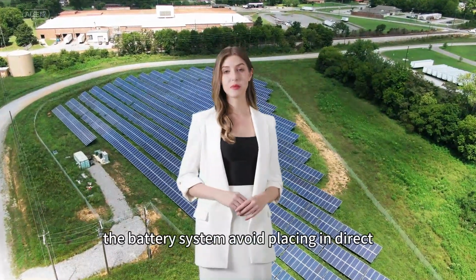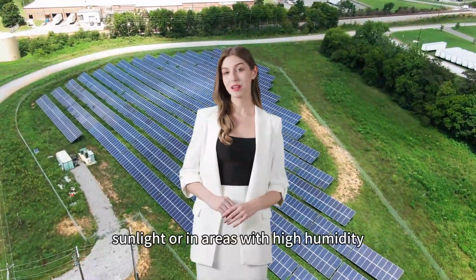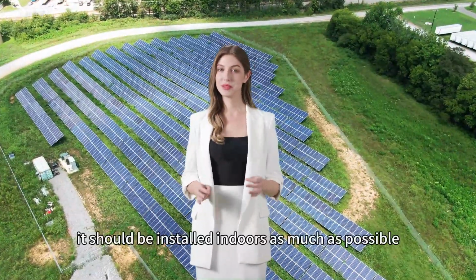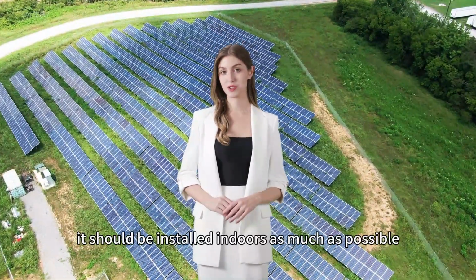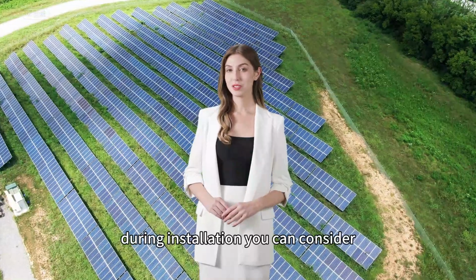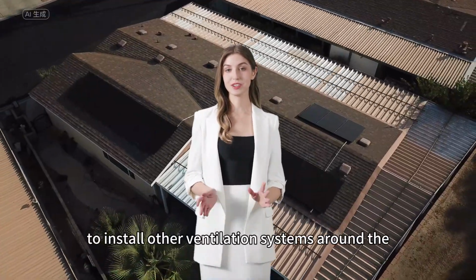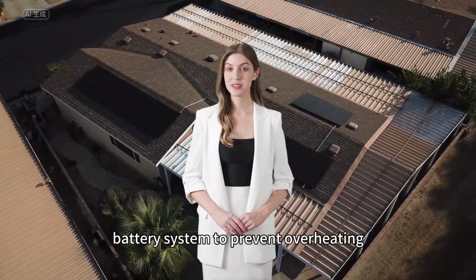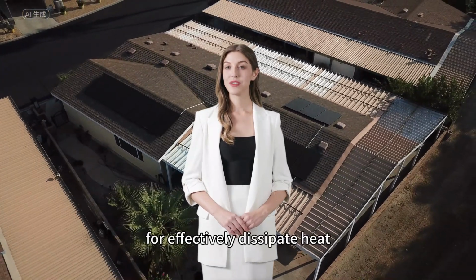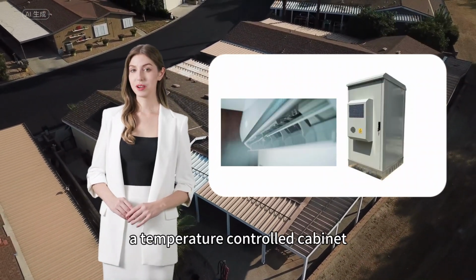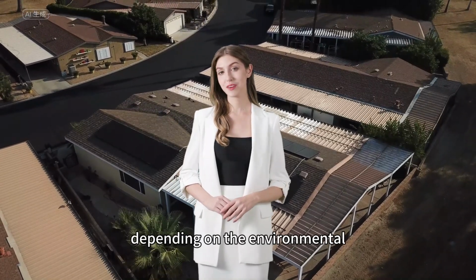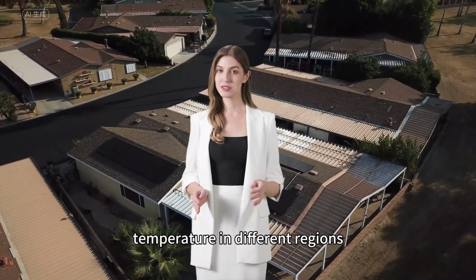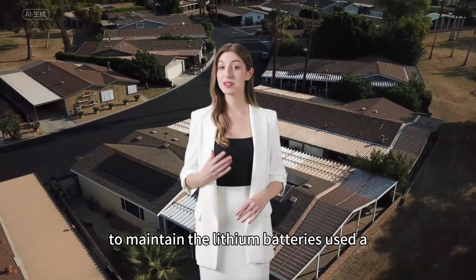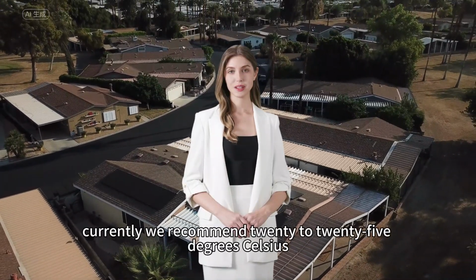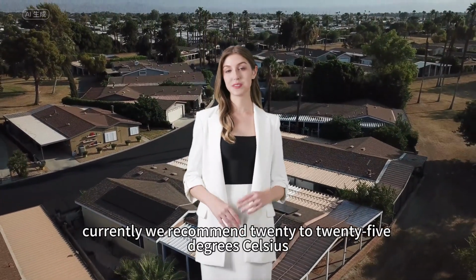For the battery system, avoid placing it in direct sunlight or in areas with high humidity. It should ideally be installed indoors as much as possible. During installation, you can consider installing other ventilation systems around the battery system to prevent overheating. To effectively dissipate heat, it can be equipped with air conditioning or a temperature-controlled cabinet, depending on the environmental temperature in different regions. To maintain the lithium batteries at a certain temperature, currently we recommend 20 to 25 degrees Celsius.